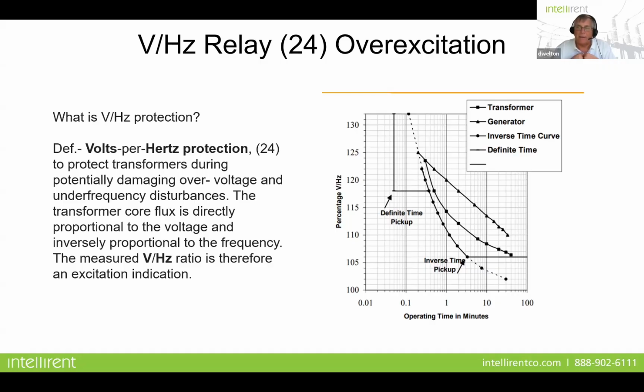It's going to see that and then start a timer. And then if it stays around long enough to cause a problem, then it's going to disconnect, because there's a lot of transients that go out on the system that can cause the volts per hertz to react. But we want to make sure that if it's not going to damage the equipment, we don't want to disconnect. Remember, that's the stability and the security part of what relays do, to not trip when they're not supposed to.